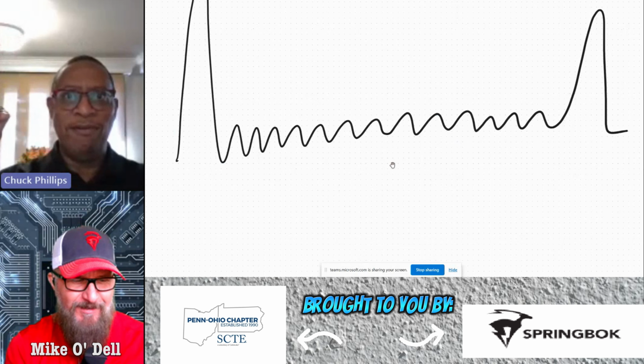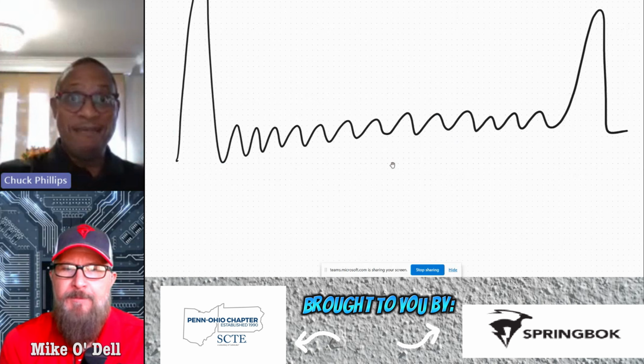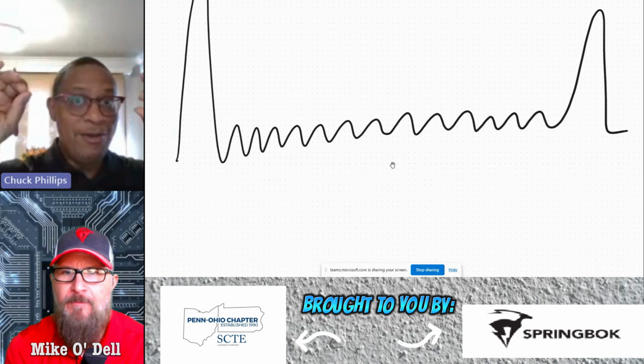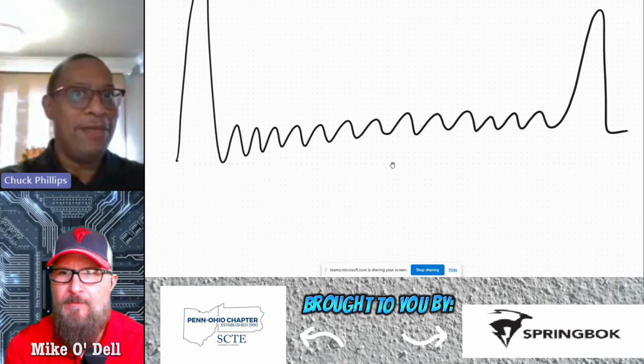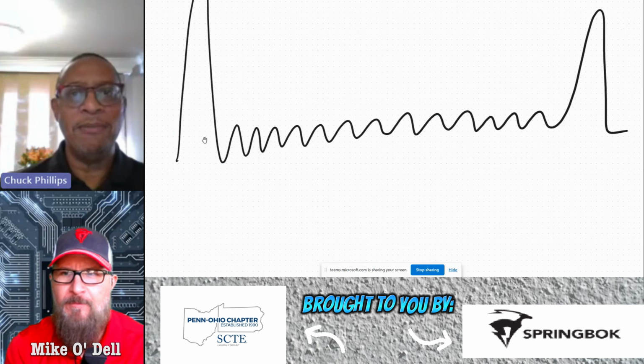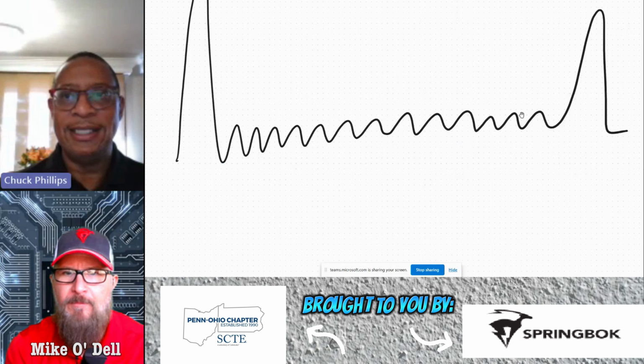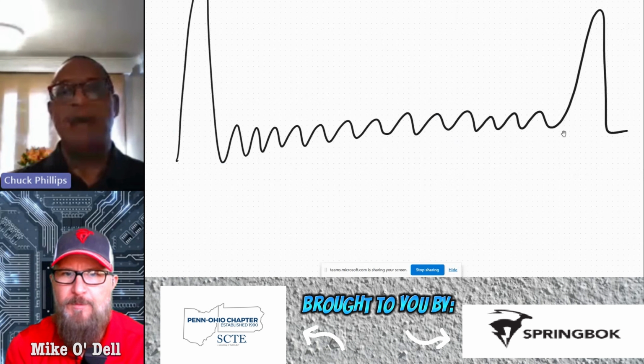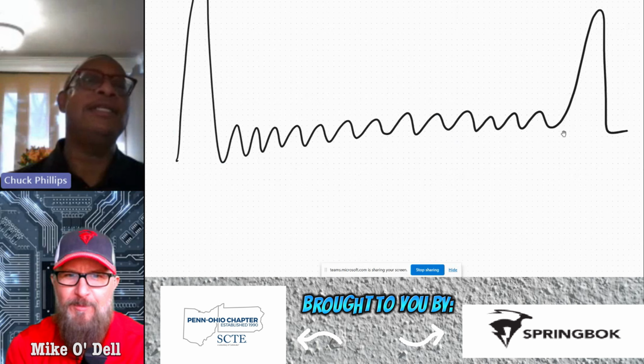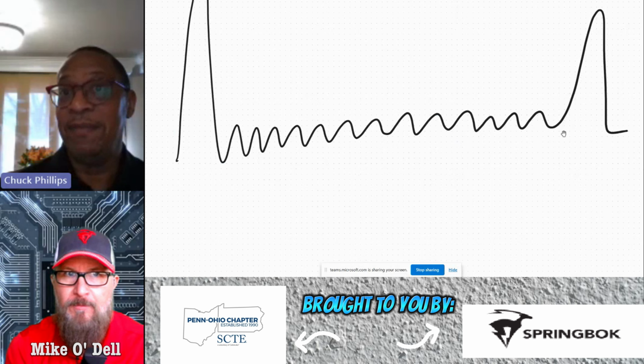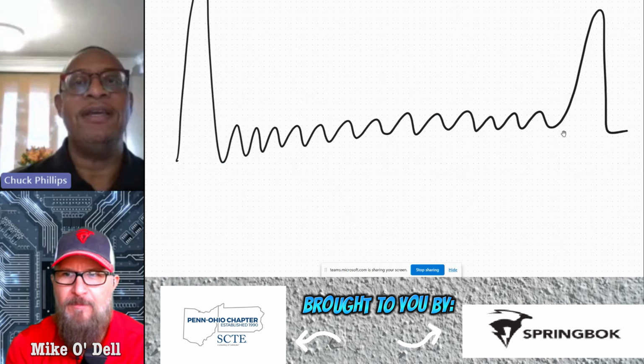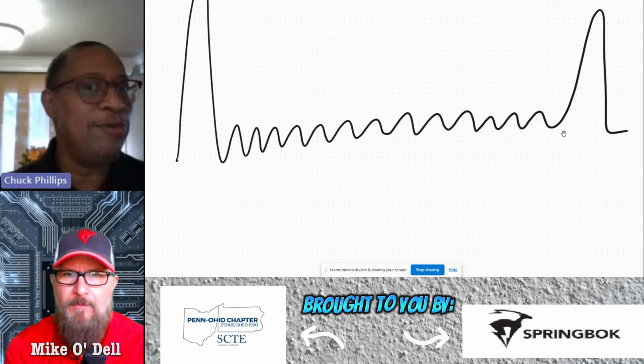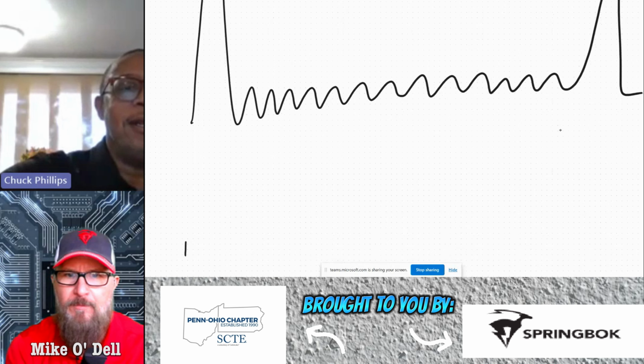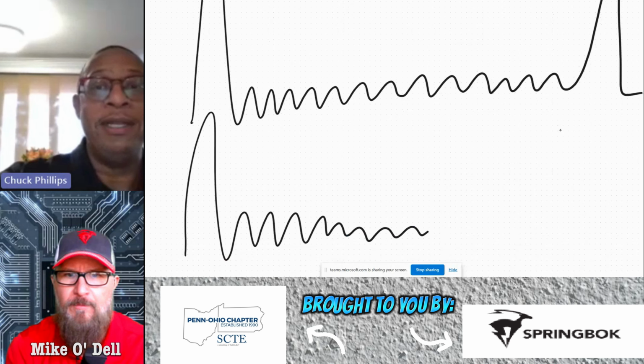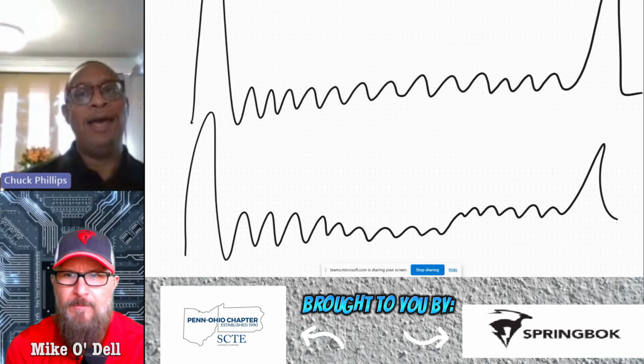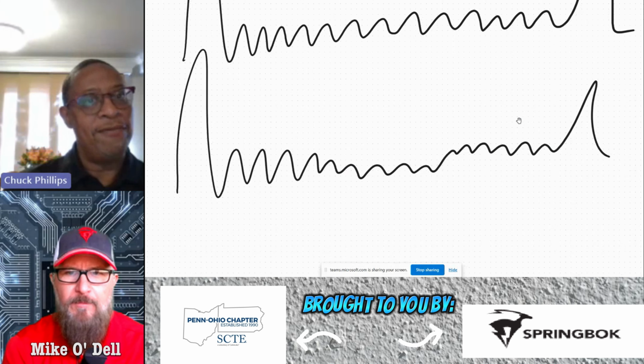But maybe if I decrease the vertical gain, or perhaps if I apply some filters, maybe if I can quiet down that noise floor, maybe I can get something to pop out that is not supposed to be there. Because the question that I'm going to ask you is, does anything on this line stand out from the rest? And you better say, no, it does not. Plus, it's entirely possible this could be AC. It could be induced AC, it could be RF, it could be nothing at all. Your vertical gain might be too high. Sometimes you can still increase the vertical gain and your whole line will be noisy, but I will ask you, does anything on this line stand out from the rest?